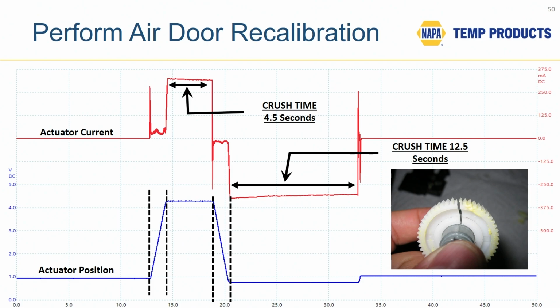Do you see in the top on the left, the high part of the red waveform, the motor is stalled for almost 5 seconds. On the lower right there, that long flat section of the red pattern, the motor is stalled, if you like, brake torqued, for 12 seconds. And that's part of the recalibration process. So by doing a recalibration, I find it very effective for picking up on intermittent electrical issues with the air door actuator motors or the circuits.